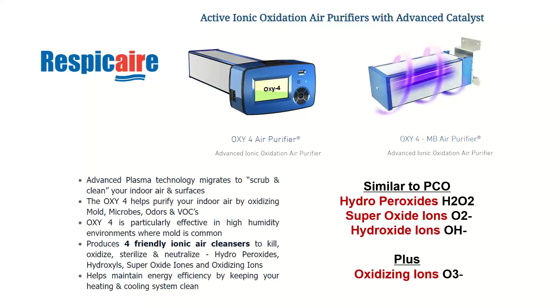So there's all kinds of versions of these, smaller and larger ones for different size applications. Sometimes you'll put in larger ones for a larger air handler. Sometimes you put 2 or 3 of these things in for even larger air handlers. At some point, it becomes impractical for like a 100,000 CFM air handler. You're not going to put 12 of these in. You're going to find a different way to do something, and we'll talk about that. But for normal stuff, 10, 20, 30-ton systems, this is a pretty good way to do it.